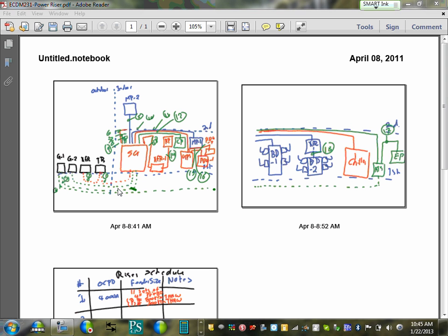And then on page, we're going to go backwards a little bit. Page 9-6 is where our NQ panels are located, and that would be the RP panel, your 208 panel. Since it's on the load side of the transformer, that one has to be main breaker. So actually, you'd be looking at page 9-7, where the main breaker panels are, the bottom part for the three-phase four-wire type.